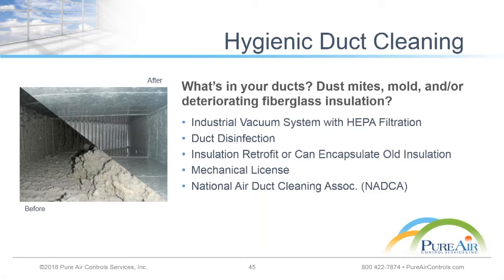And also the exhaust duct in some cases as well. A couple examples where you see this: when new air handlers are put into a system but the old ducts are left there, the extra air volume blowing through old ducts that have accumulated dirt and debris over the years blows stuff out of the vents. You see that quite a bit. So environmental duct cleaning is a very key piece of maintaining the efficiency and the sanitary hygienic condition of your air handler system.